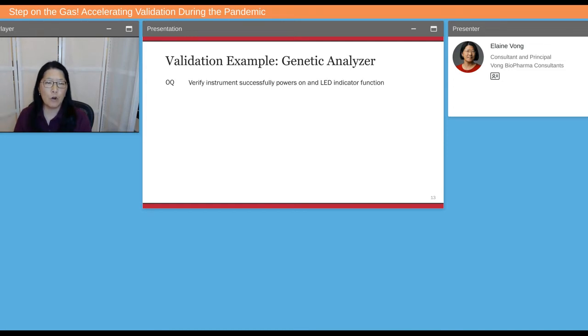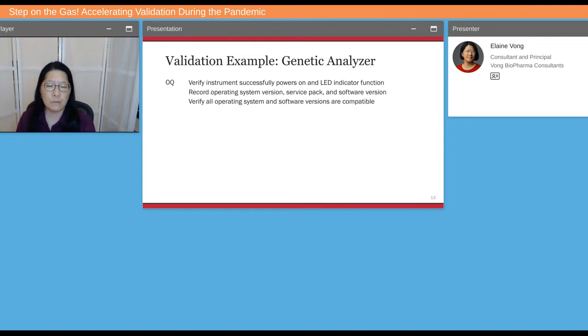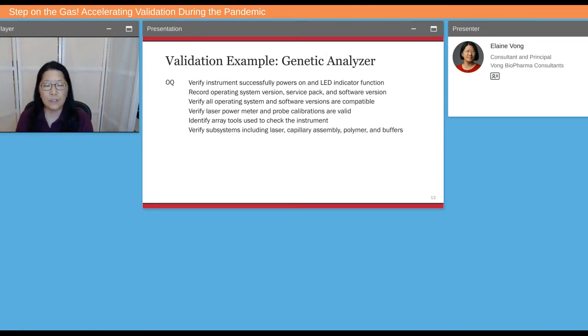So for the OQ for the genetic analyzer, we would verify that the instrument successfully powers on and that the LED indicators all function. Record the operating system version, service pack, and software version number. Verifying all operating system and software versions are compatible. Verify that their laser power meter and probe calibrations are valid. Identifying array tools used to check the instrument.